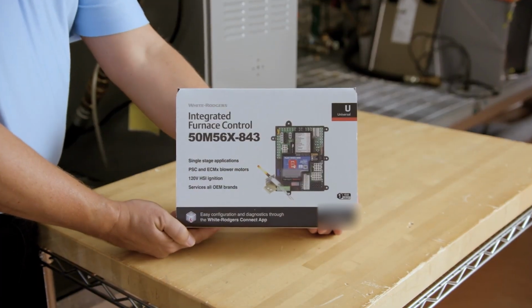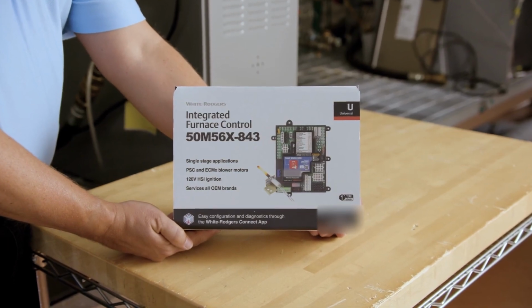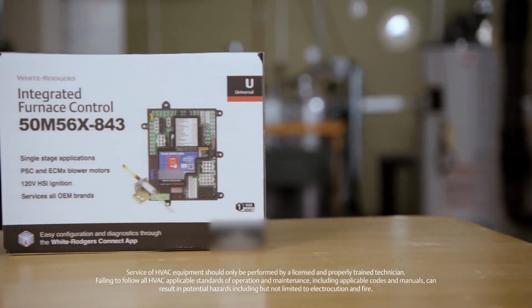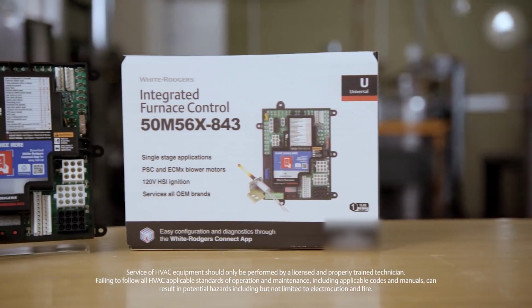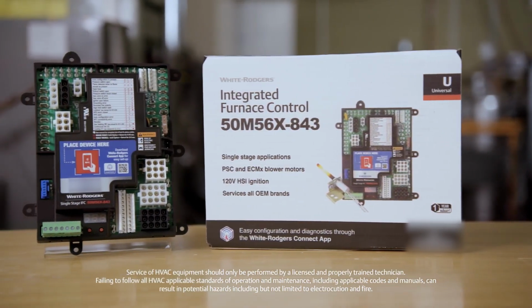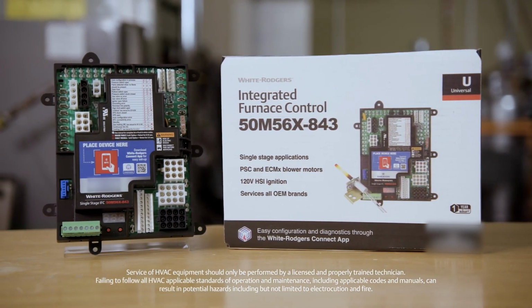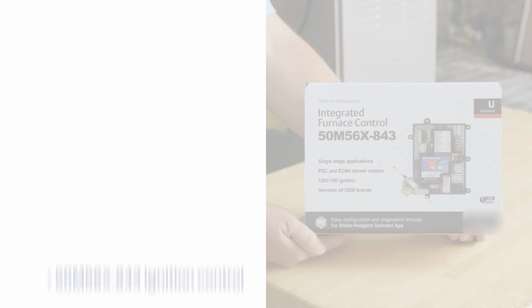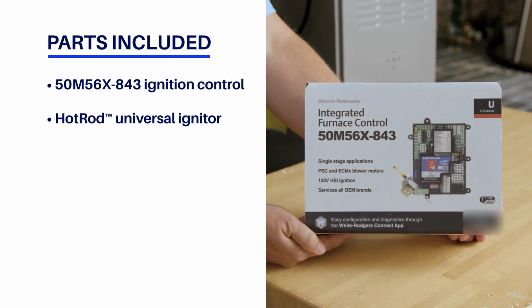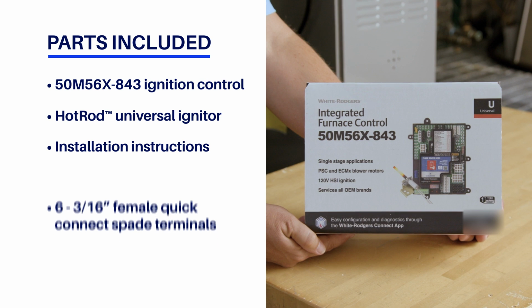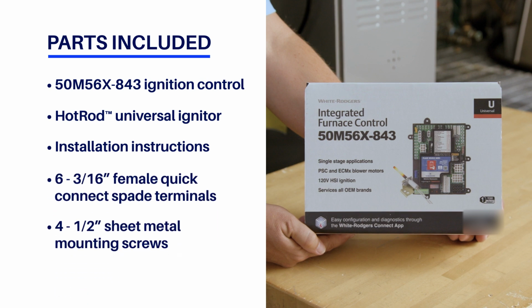This is the installation video for the White-Rodgers 50M56X-843 Universal Integrated Furnace Control by Copeland. The kit includes materials needed to replace or upgrade many single-stage hot surface ignition integrated furnace controls. The control can be used for both PSC and ECMX blower motor applications, and with having the most connector terminals on board, eliminates the need for adapter harnesses.